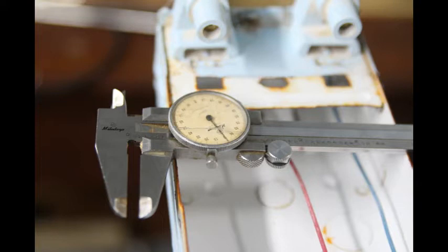For some reason, as the Chinese manufactured these tubes, they did not conform to the standard of what an FA-8 fixture should be. I found a document indicating that it should be .32 inches for the pin that goes into that recess, and none of these Chinese manufactured tubes will come anywhere close to .32 inches.